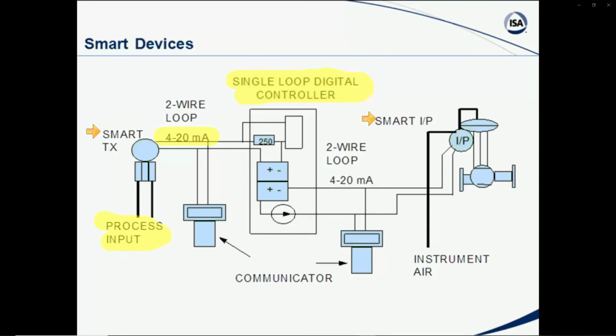we also have the capability within that particular device, the smart transmitter, to perform calculations, square root linearization. We can store historical data and curves. We can check calibration and see how things are operating, and even then we can use a handheld communicator back in the control room or at some location to actually communicate with the smart device, rearrange it, check for diagnostics, etc., etc. So there's a lot of advantages, and by the same token, the smart valve packages or smart I/P's have the same capabilities with the microprocessors, so on and so forth.